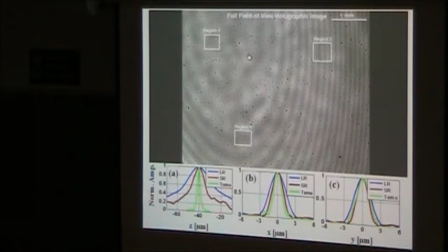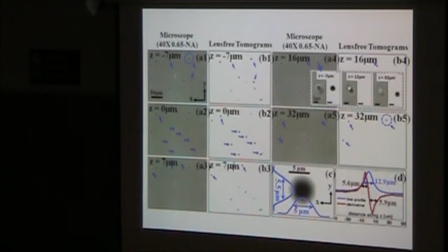This is not dual axis, so the resolution will not be as good. And also this is a very inexpensive way of putting it, so it's not as good as the previous benchtop. It has more artifacts, but still it provides us a decent field of view and a decent depth of field. And these are actually some tomographic movies captured with that microscope where, again, we're slicing here the particles. The resolution here is not as good as the previous one, axial resolution. It's sub 6 micron, a factor of 2 worse than the previous one, mostly because it's single axis, and there are more artifacts because of the cheaper design of this microscope. But still, it performs a nice depth rejection ability compared to a conventional single axis microscope objective.